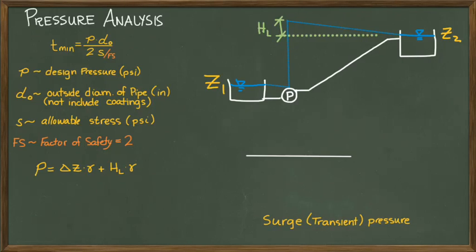Let's assume that you have water traveling down a pipe at velocity V. In a short time, the valve closes in the pipeline causing the water in the pipe to crash into the valve. Depending on the velocity, the pipeline reacts by expanding slightly and then creating a return wave headed in the opposite direction. This return wave then bounces its way back through the system, pounding every pipe fitting like a hammer, which is why it is often called water hammer.